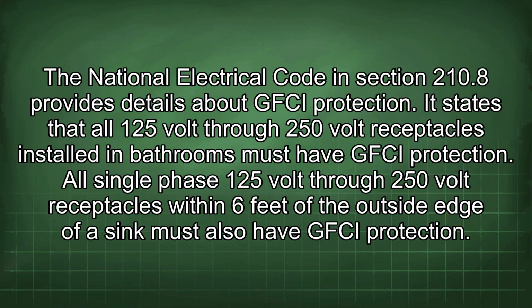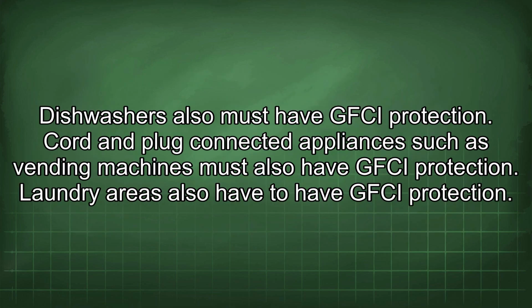The National Electrical Code in Section 210.8 provides details about GFCI protection. It states that all 125V through 250V receptacles installed in bathrooms must have GFCI protection. All single-phase 125V through 250V receptacles within 6 feet of the outside edge of a sink must also have GFCI protection. Dishwashers also must have GFCI protection. Cord and plug-connected appliances such as vending machines must also have GFCI protection. Laundry areas also have to have GFCI protection.